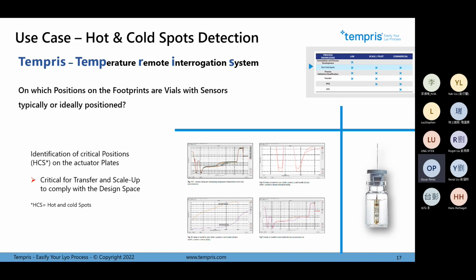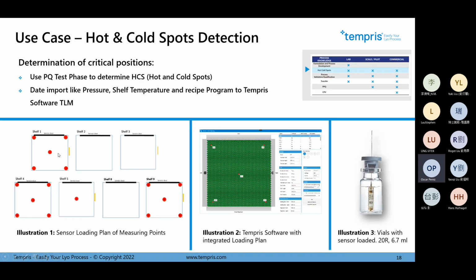So maybe we can do, for example, here we have a customer that wants to keep the five sensors, but only in the top, middle, and bottom shelves as a reference. It was a freeze dryer with 9 shelves, 20R vials with 6.7 ml, and they wanted to measure the five sensors in the top, middle, and bottom shelf, and one additional sensor in shelf 5. We put the antennas in this freeze dryer in these different positions. We had this configured before, and then we will see what the results were.